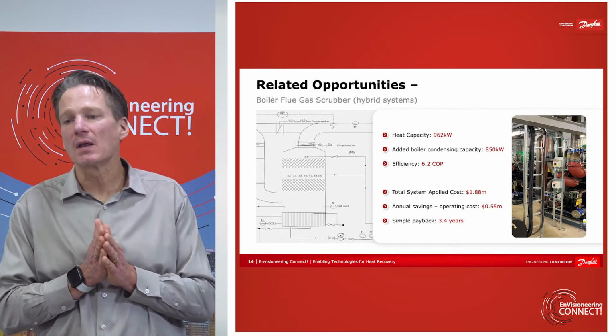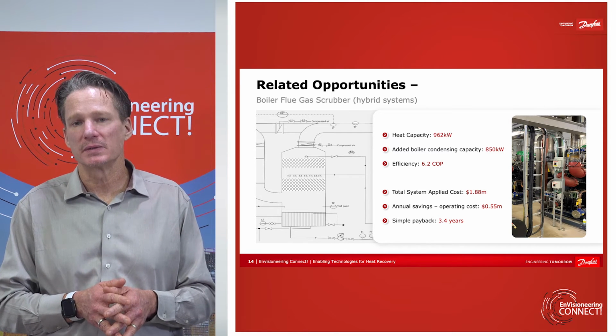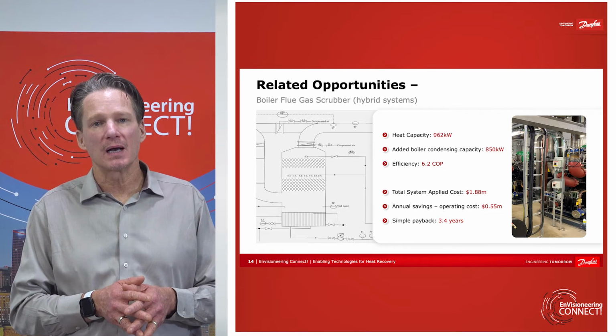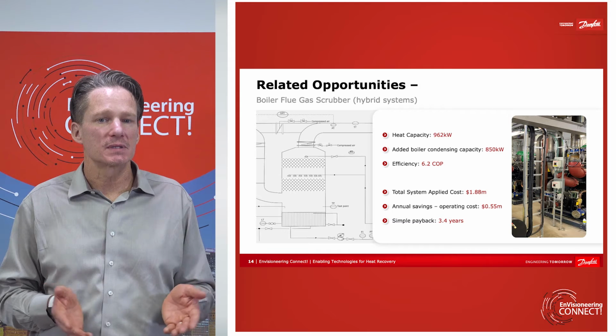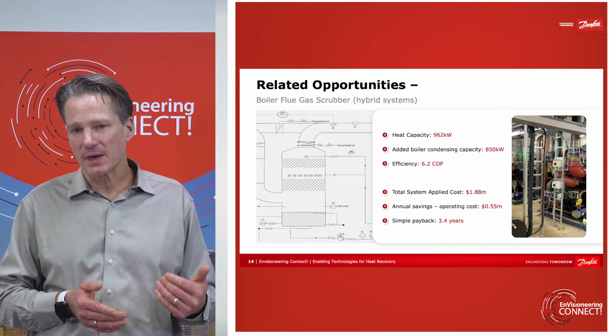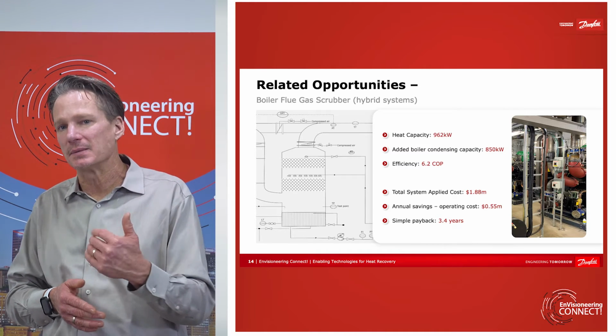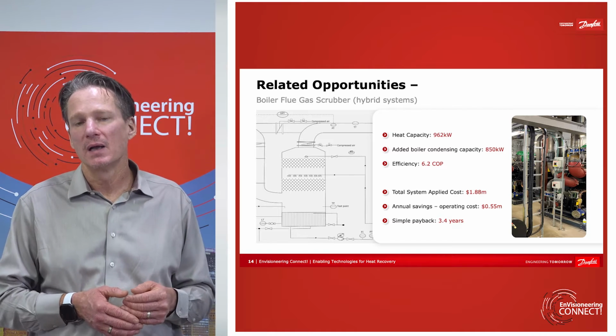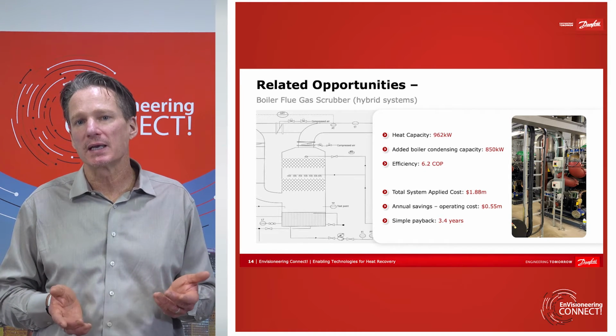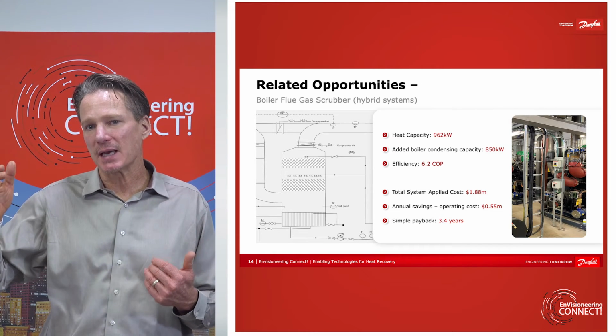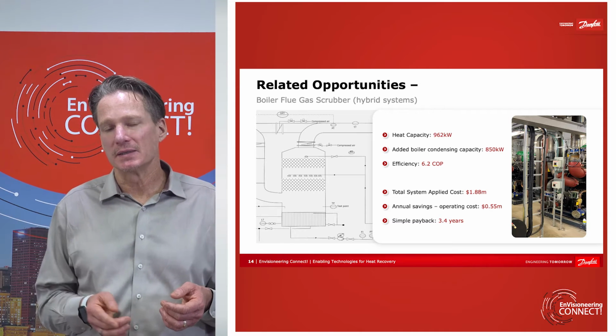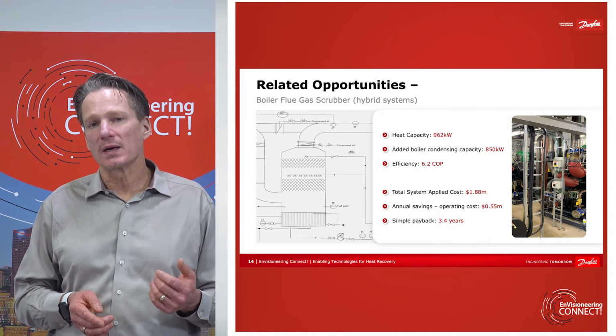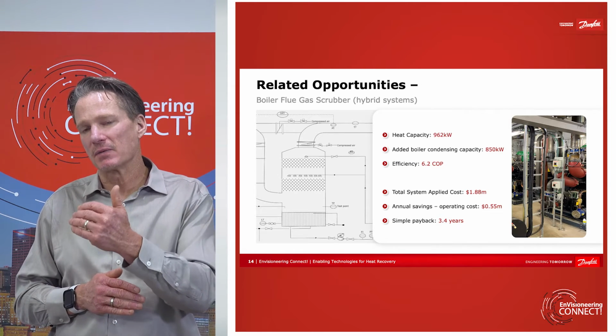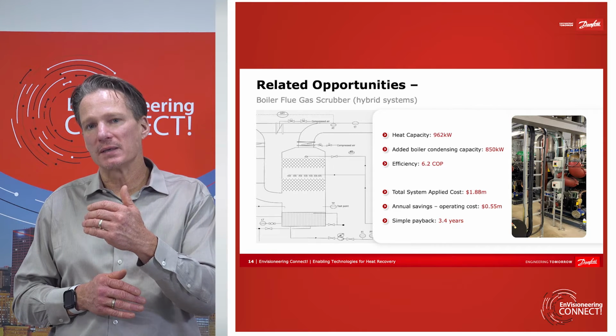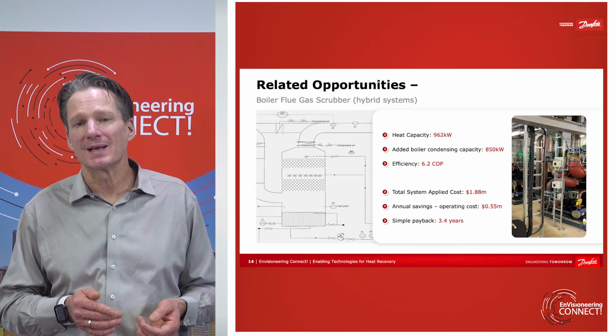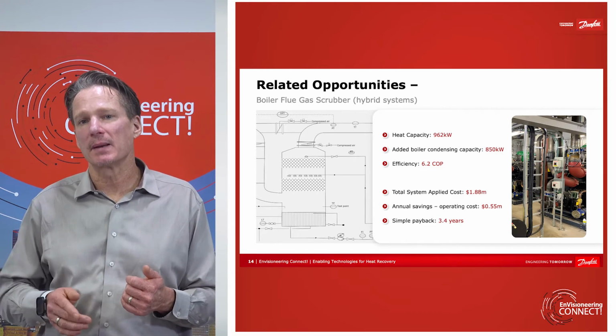Another related opportunity: you'll hear a lot about dual fuel systems or hybrid systems in the future. Most of what that's speaking to is it's not always possible to fully electrify the heating systems. Industrial processes, for example, it's very tough to electrify all of them because of the high heating temperature demand that they have. A boiler or a furnace that you're replacing, the fossil fuel sources, they didn't care what heat temperature they were producing. It was about the same efficiency at 100 degrees C as it was at about 60 degrees C. So the difference is that a water-to-water heat pump cares. Every 1 degree C differential that you go up, or 1 K, in temperature, the corresponding heat pump efficiency is going to go down by about 2%. So that business case, when you get to that industrial application, goes down a lot.